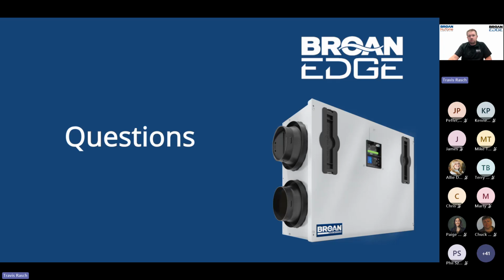All right, looks like something came in. Sabina asks, since there's no motorized damper, are there any damper-related error messages for this model? Sabina, no, not directly. If there is an airflow-related error, let's say that damper, whether it's our gravity damper or a motorized damper somewhere else in the ductwork, the error you're going to see is the airflow error, whether for supply or exhaust, meaning the airflows that were set are no longer achievable. That could be the motorized damper not functioning the way it was intended, or a gravity damper not functioning the way it was intended. So there's not going to be a direct error code related to the damper. You're going to get a correlated error code for the supply airflows not being met.